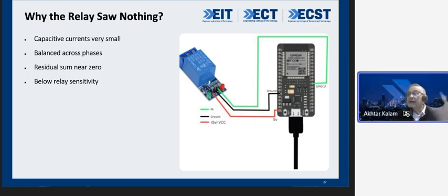Capacitive current was very small, so the relay did not see anything. I told you in the beginning, I said everything was balanced, no problem. The sum of residual was zero, and the sensitivity of the relay was below that, so it did not operate. That's exactly what happened. It saw nothing, it did not operate.